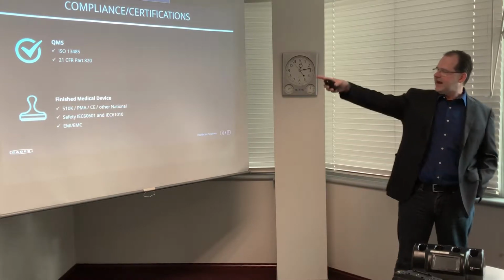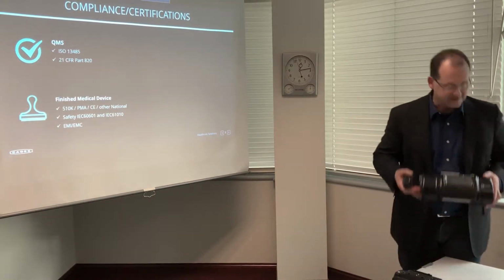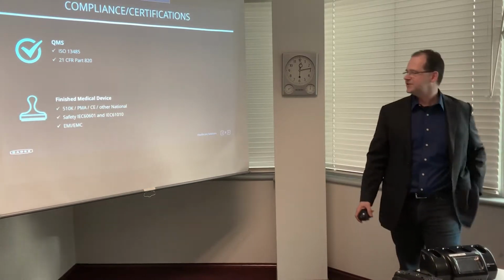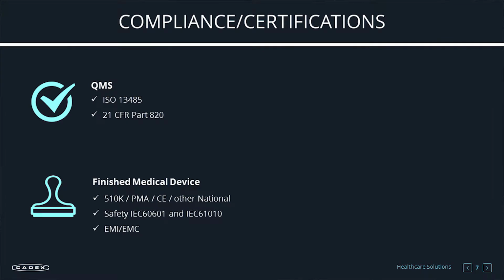The second item is the actual finished medical device. When we build a product like this, it needs to pass all kinds of different certifications. The big milestone for the complete medical system is the 510K, or pre-market authorization for the US, for North America. That is the official go-ahead from the FDA to our final customer that they are allowed to market and sell this as a medical device. Until they have this, they are not allowed to market and call this a medical device. It's the really key benchmark that gets them from having just a project and some R&D to an actual product, so that has line of sight to revenue.